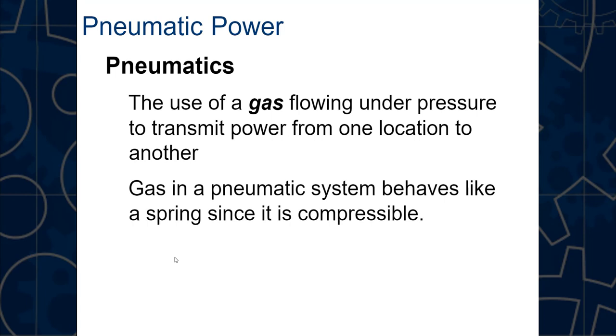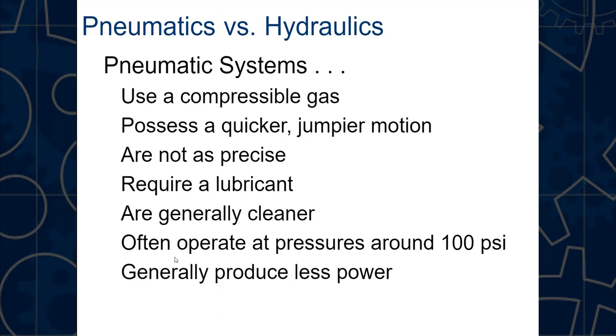The biggest thing to remember is that pneumatics uses air or gas, while hydraulics uses liquid. Gas also acts more like a spring when compressed. Pneumatics uses compressed gas or air, produces quicker or jumpier motion than hydraulics, is not as precise, requires oil in the system occasionally to keep rubber o-rings from drying out, is generally cleaner, typically operates around 100 psi, and produces less power — so you won't see it used for forklifts or construction equipment.